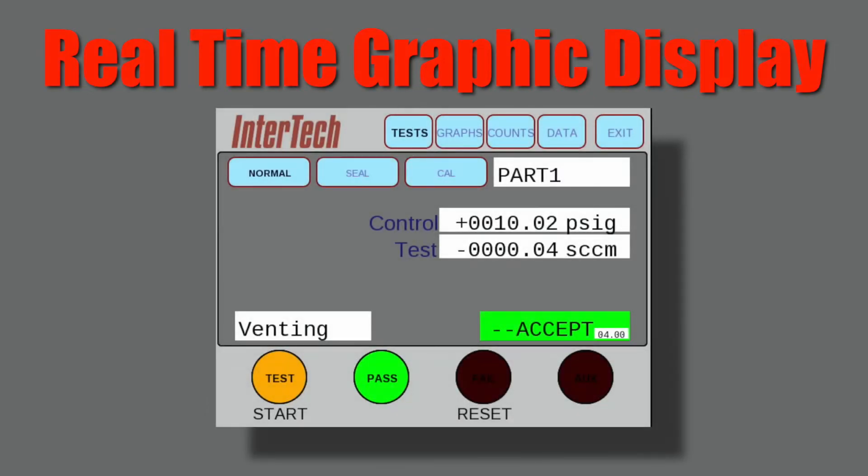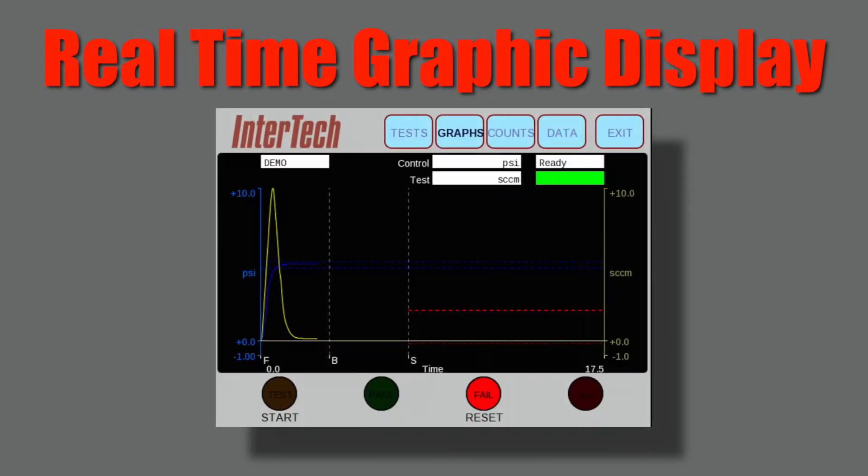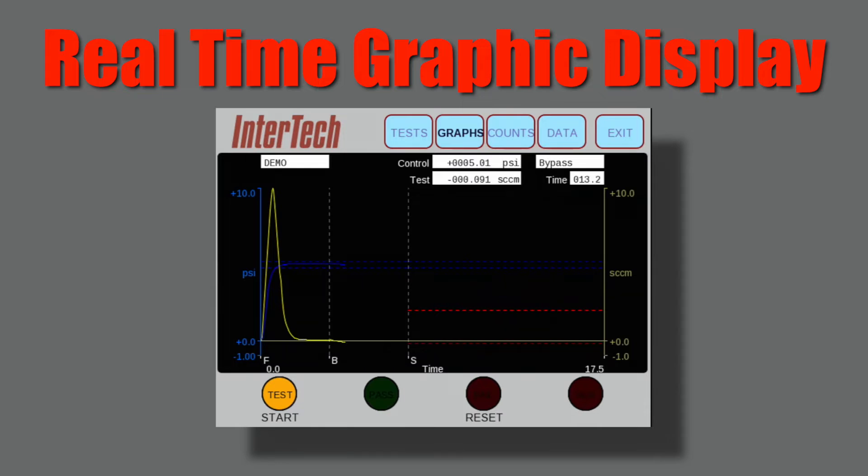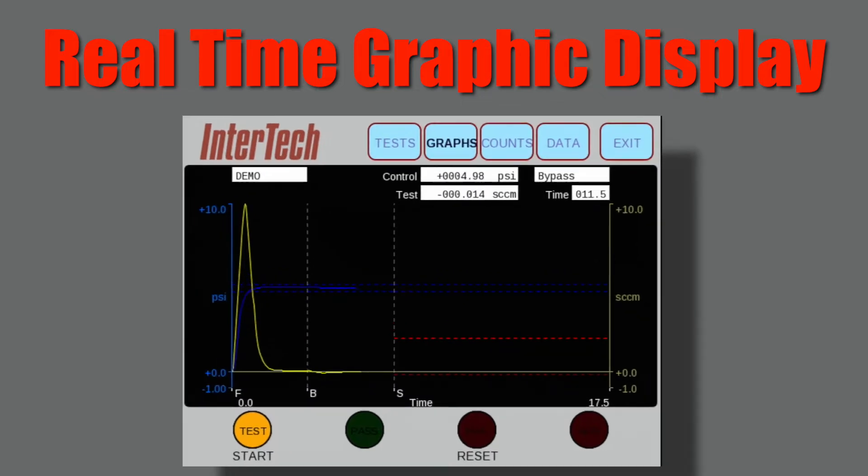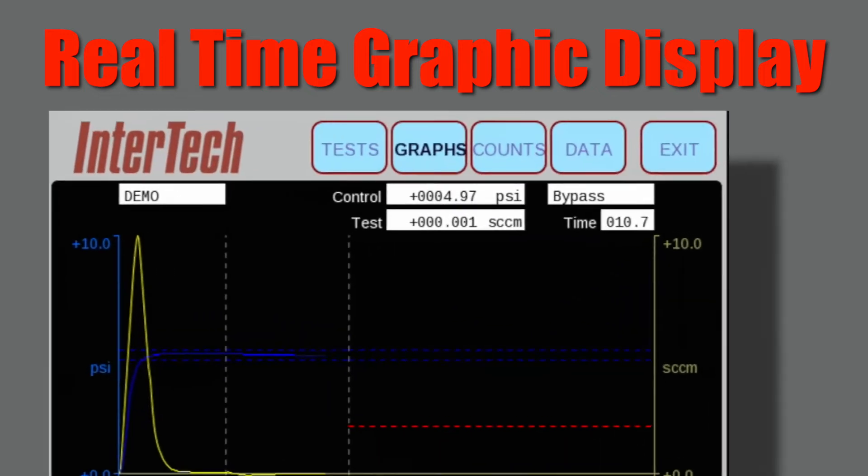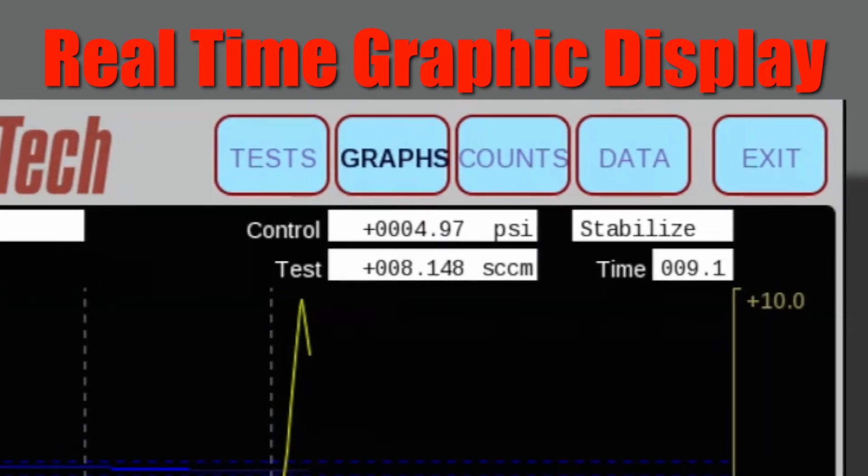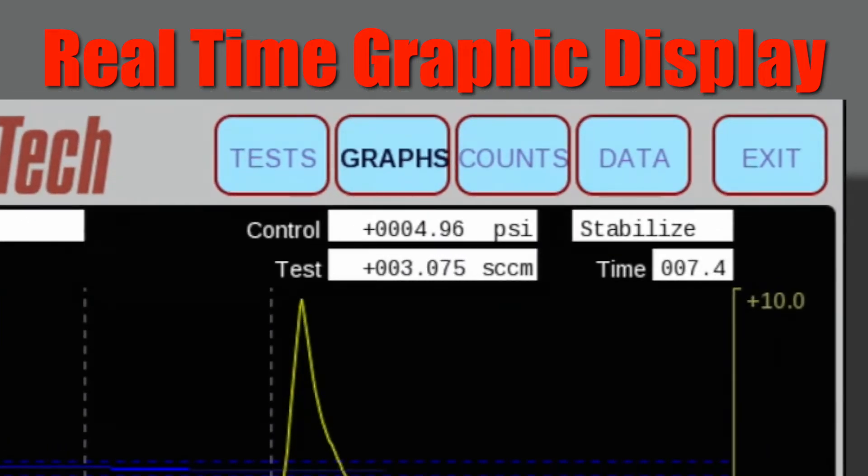When the graphs button is selected, the operating buttons remain available. Pressing start, the real-time test cycle graphic display allows the operator to see the leak rate flow curve as it develops during the test, while still displaying the operation mode and test values numerically at the top right of the screen.